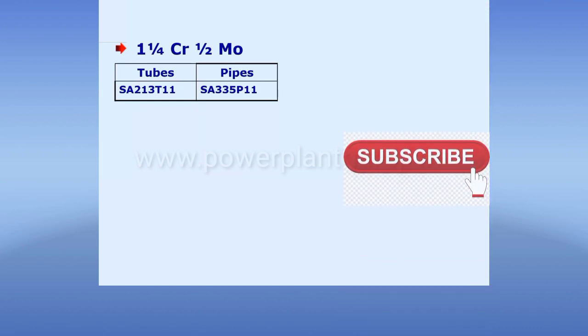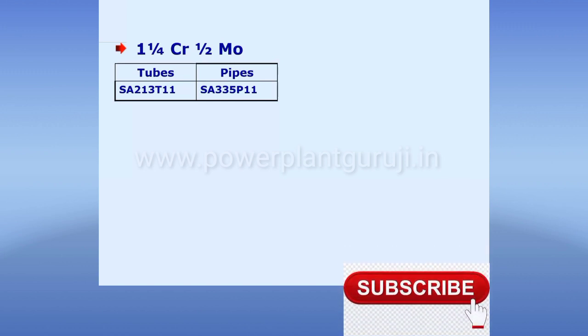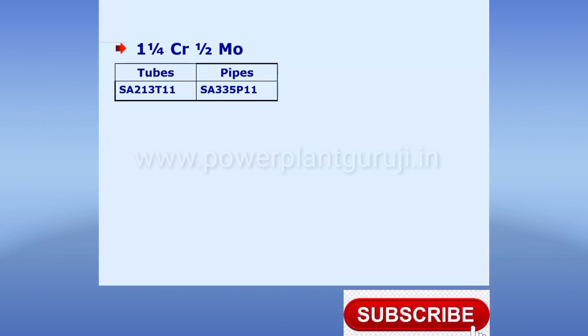Usually this metallurgy is used where the component temperature is not to exceed around 500 degrees centigrade. So up to around 500 degrees centigrade we can use this, and designers are using this. But wherever the metal temperature is expected to go beyond 500 degrees centigrade — 510 degrees centigrade — then T11 cannot be used.